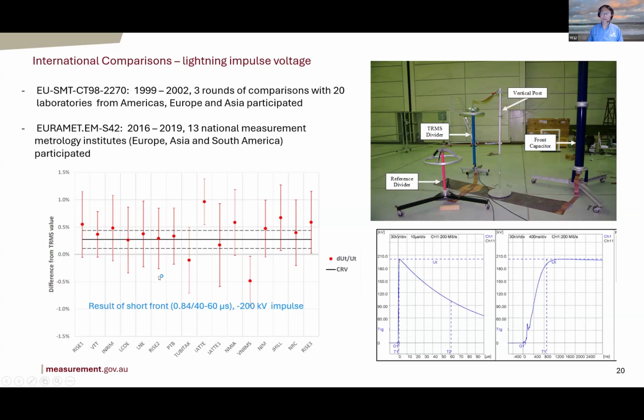So this is the result for the second comparison. You can see this is a peak value difference from the so-called transfer reference. The reference value uncertainty is 0.4. A lot of laboratories exceed that. So some of the CMCs are a bit ambitious. I think the reason for that is because the voltages are produced by individual laboratories. They have different noise, different dispersions. That puts extra uncertainties into the results.